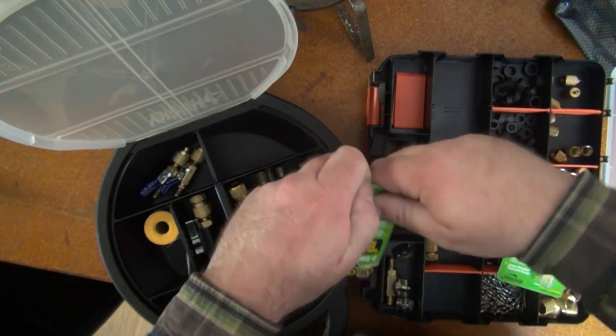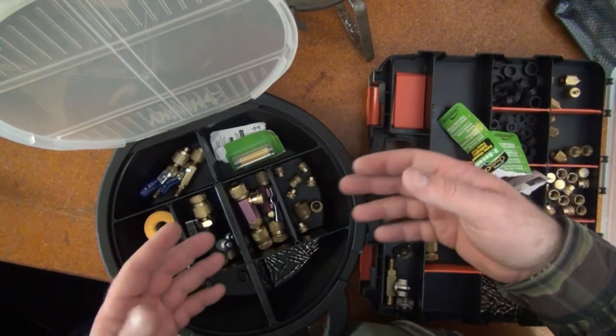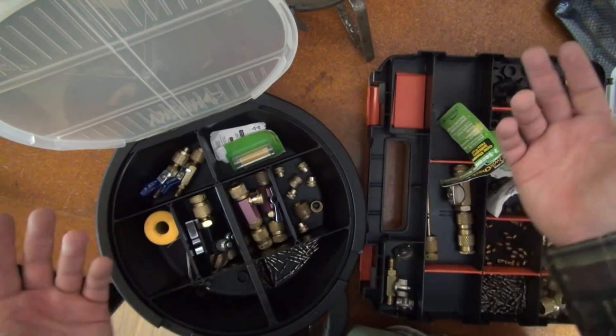A good measure might also be to throw a couple of quick acid tests in before you throw your recovery machine on a piece of equipment. Those things aren't bulletproof, but they're a good indication. And if you have a bigger container, you can throw in the more advanced acid test kits if that's what you want to go with.